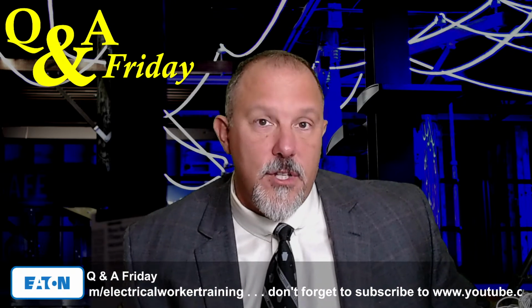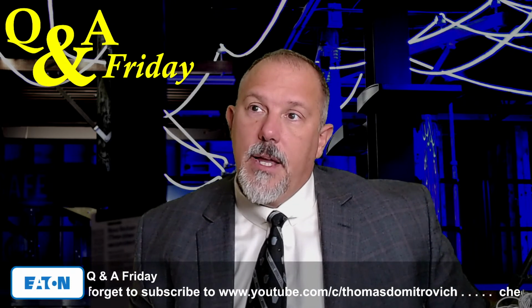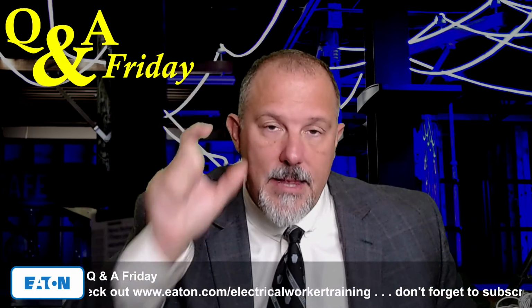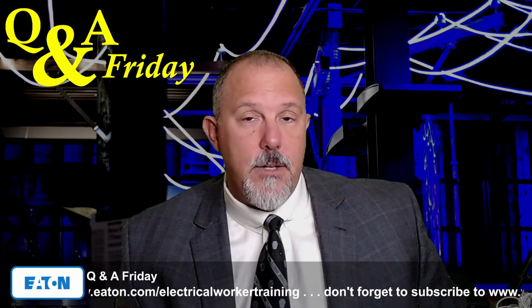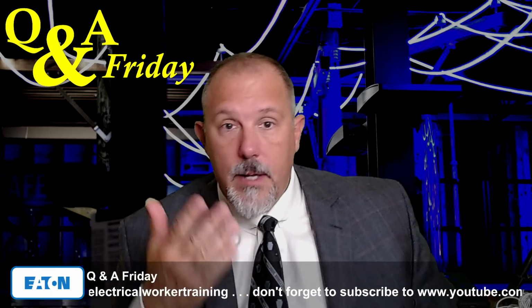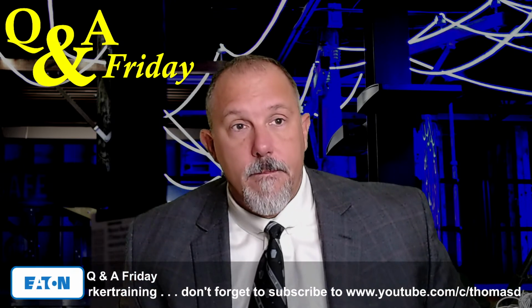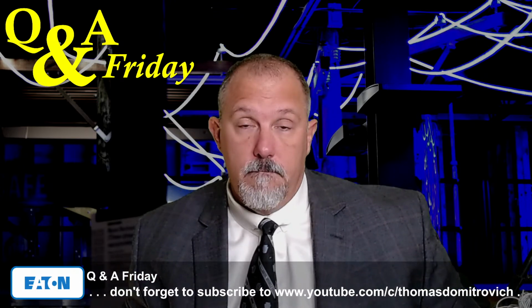Because I can't exceed the voltage, but I can go lower than the voltage. So I couldn't find a problem there. And then there was nothing in 408 that I could find that said that a three-phase panel has to be used at three-phase. And there was nothing in the instructions from the manufacturer that said it's a three-phase panel and it cannot be used in a single phase. If I decided to only use 2 legs in that panel, then I don't see any place. And you guys and gals can help me. Where in the code would it be prohibited? And I can't find any place.